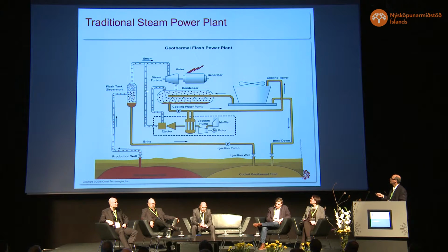Part of the steam is used for the ejectors, together with the vacuum pump, to draw the NCG out of the condenser. Probably this is the most complicated part of the equipment, besides the technology of making the turbine, mainly the materials appropriate for the characteristics of the steam. The brine can either be flashed to a second flash, with the steam going into the middle of the expansion, or go back to the injection well.